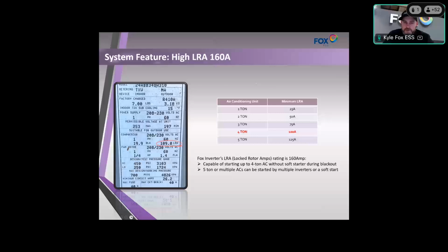It's really important when you're doing batteries to know what the customer needs. If they have 5 fridges and 5 freezers, 2 air conditioners, a pool pump with a heater, and whatever else, all that stuff stacks up. So knowing every start capacity and running capacity matters — your running capacity is your RLA. For example, this takes 20 amps to continuously run, but 110 amps to start.